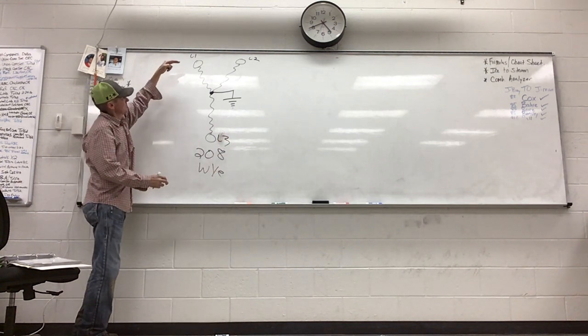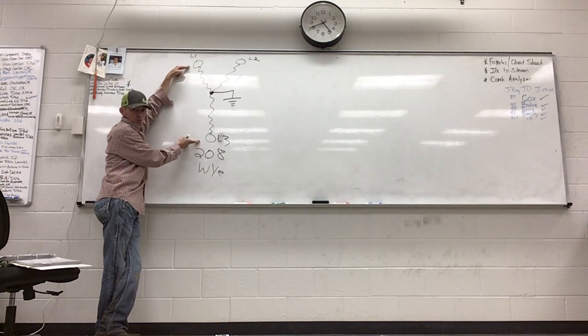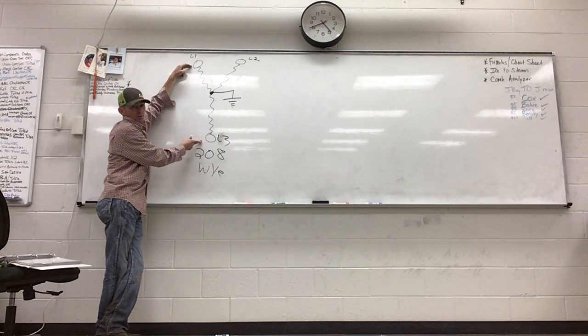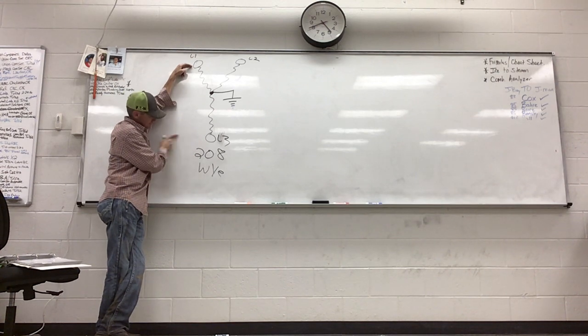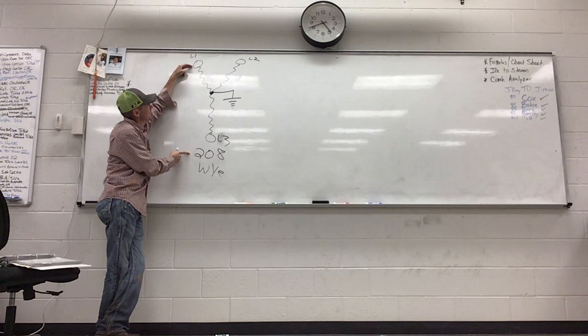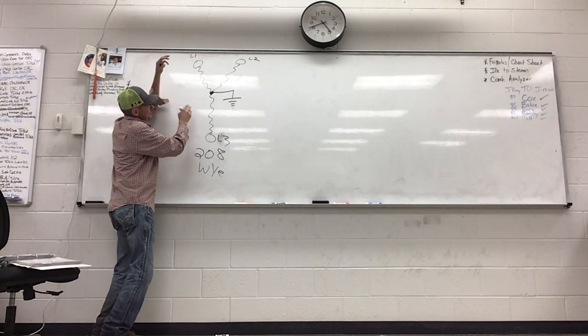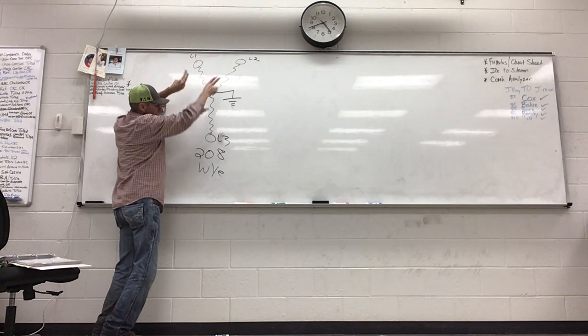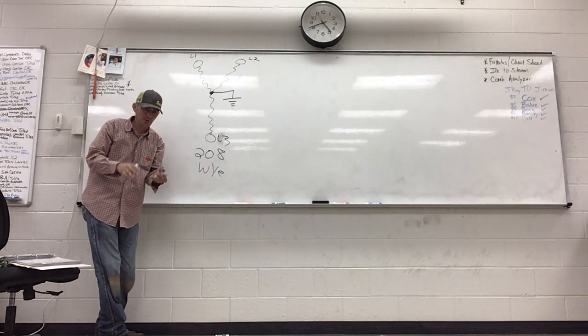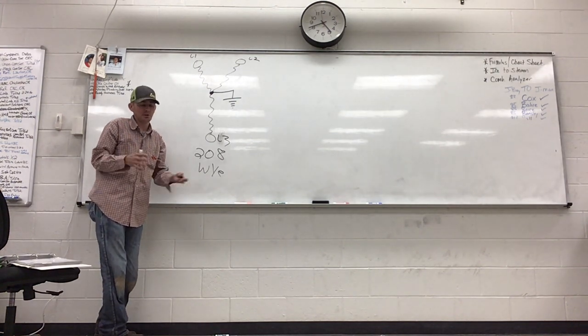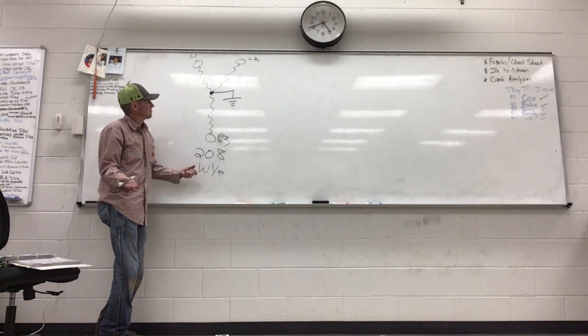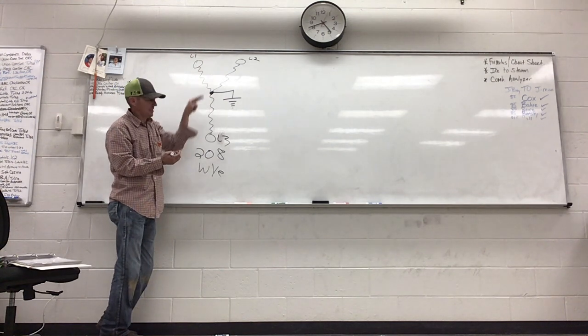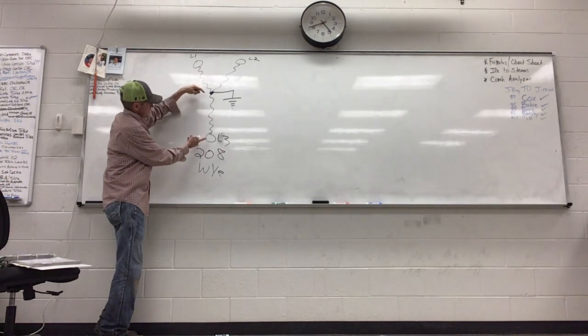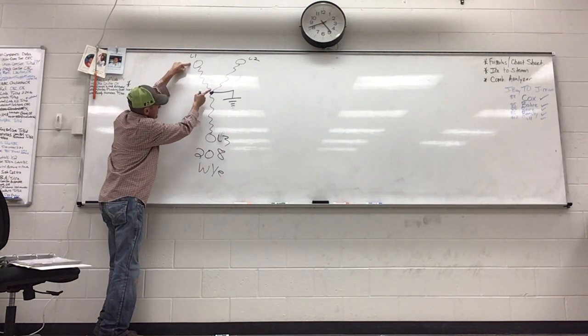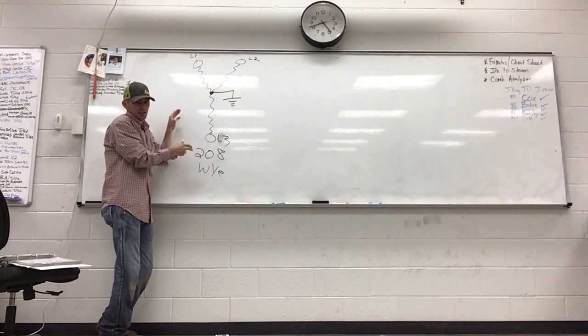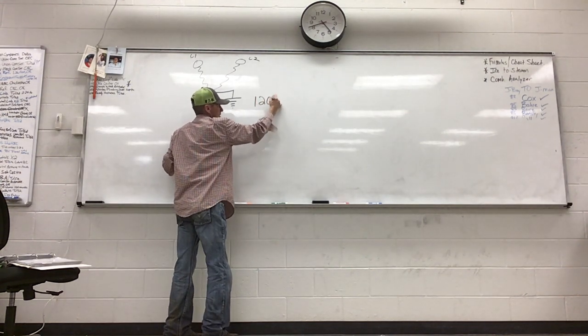So now, if I go from leg to leg on this 208 building—if I go from L1 to L3—what voltage should I see? I should see 208, right? And here's the thing: when I go from any leg to any leg, 1 to 2, 1 to 3, 2 to 3, I'm going to get 208 on this 208 building. If I go from any leg to neutral or ground—3 to neutral, 1 to neutral, 2 to neutral—I will get 120 volts.